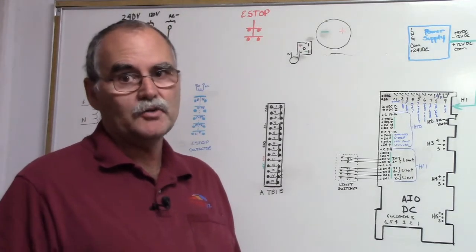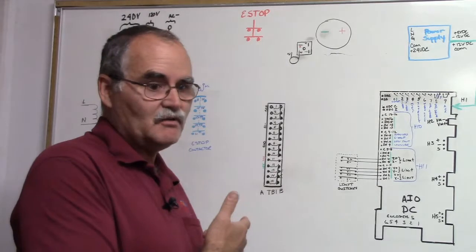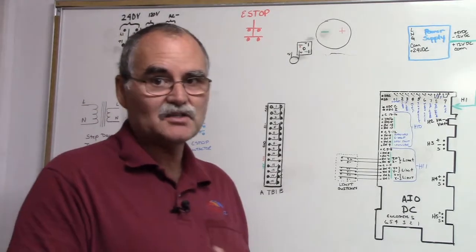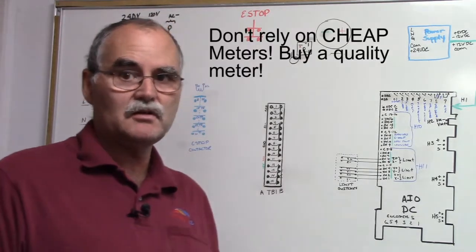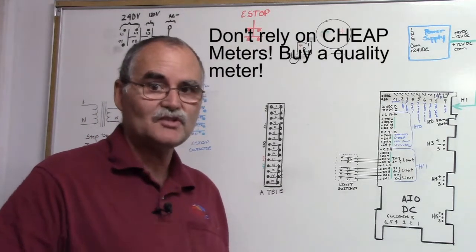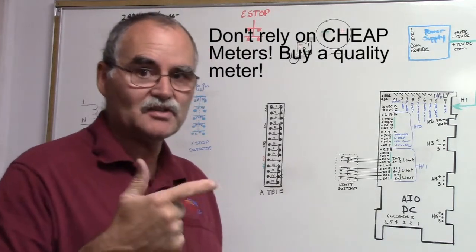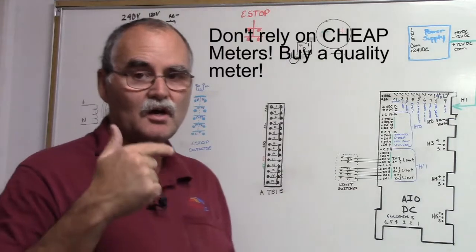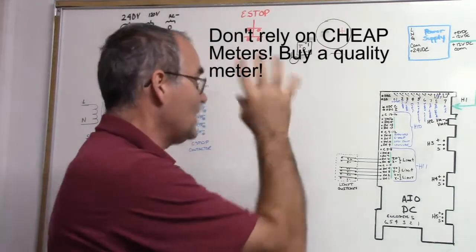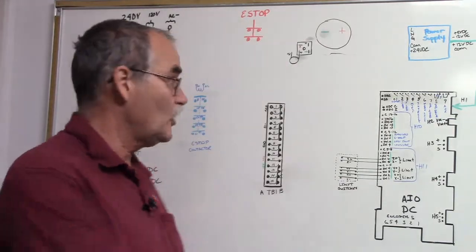Make sure that your meter is reading correctly and it's working properly before you go testing something. The last thing you want to do is put your meter there and you think it's dead, and it's not because a fuse is blown in the meter, the meter's malfunctioned. So make sure you test your meter, make sure you test your test equipment on known voltage sources before you test on whatever it is that you're testing.